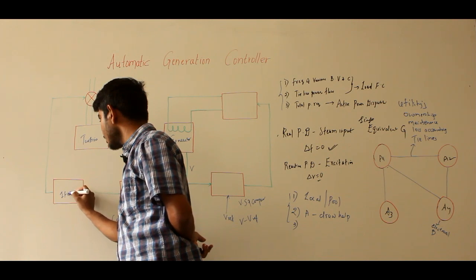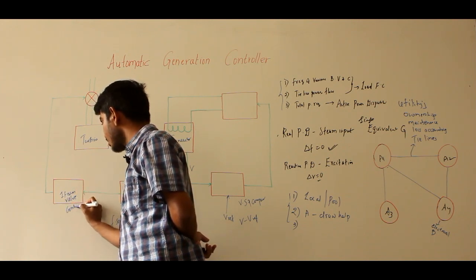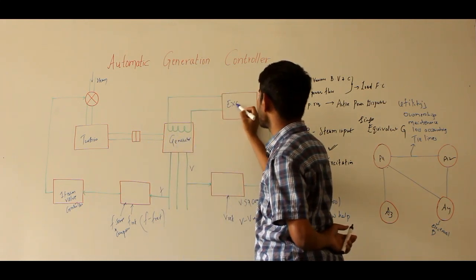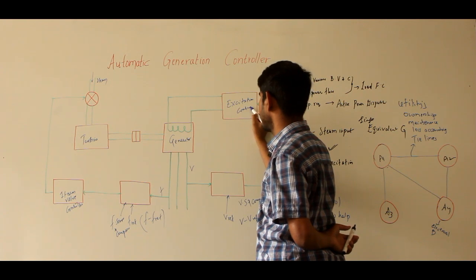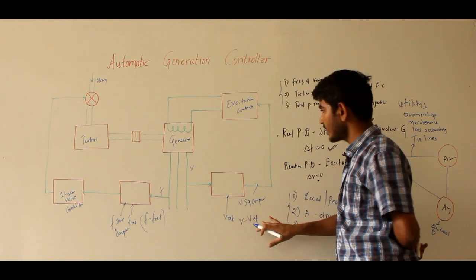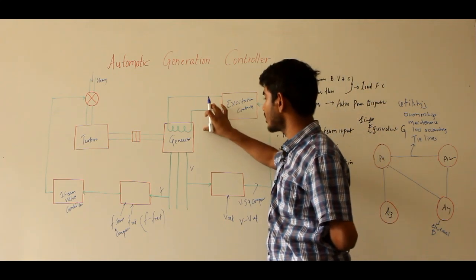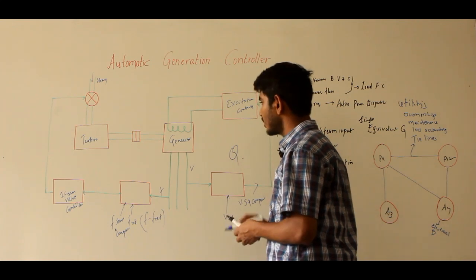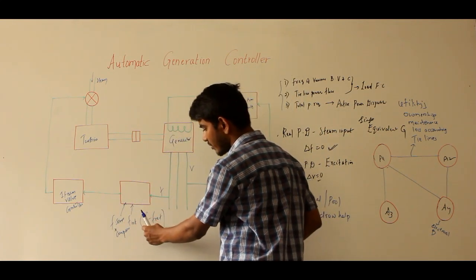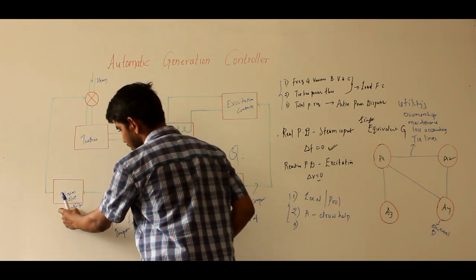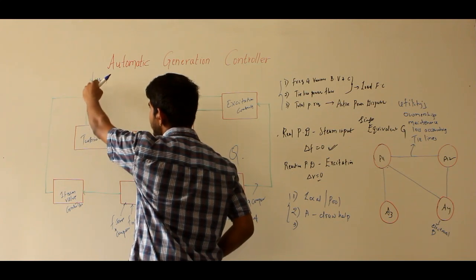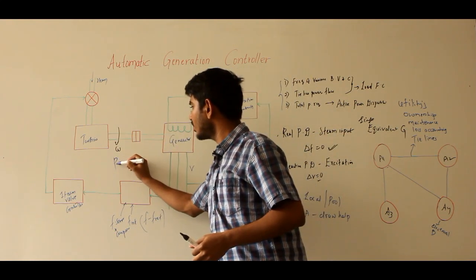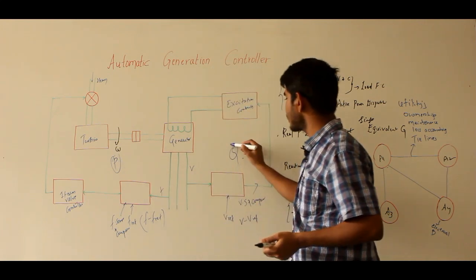The difference is fed to the steam valve controller. You can see this is the input steam, and here we are having the excitation controller. The difference between V and V reference is given to the excitation controller, and the excitation controller regulates the machine excitation. This part is regulating your reactive power. For the frequency part, the frequency sensor and comparator — F minus F reference — is fed back to the steam valve controller, and this steam valve controller opens or closes the steam valve so that steam flows to the turbine rotating at omega. This is how it controls real power generation and reactive power generation.